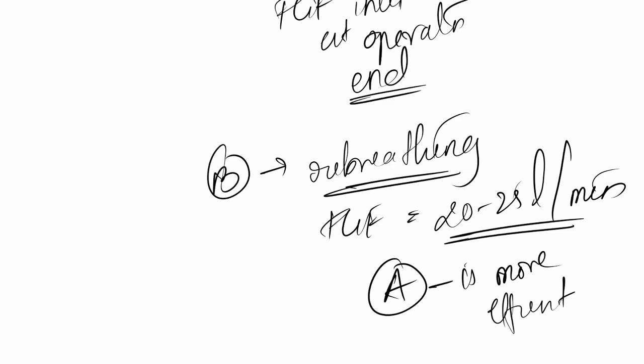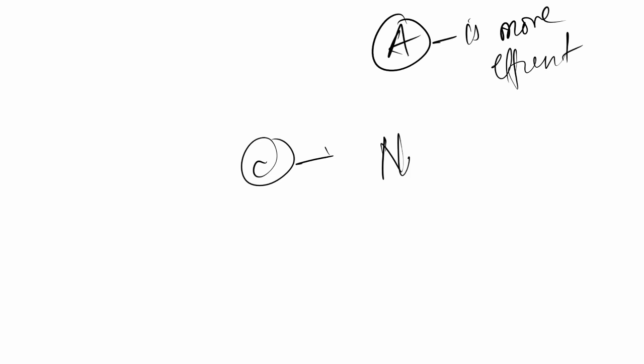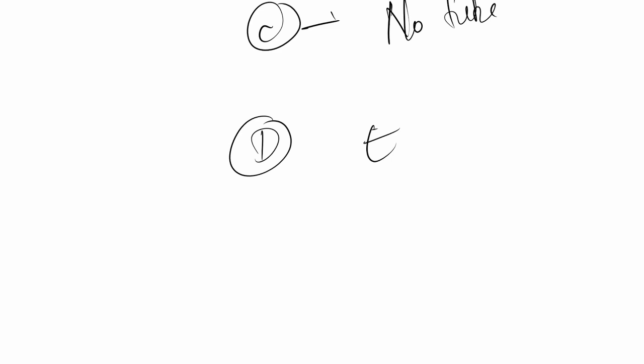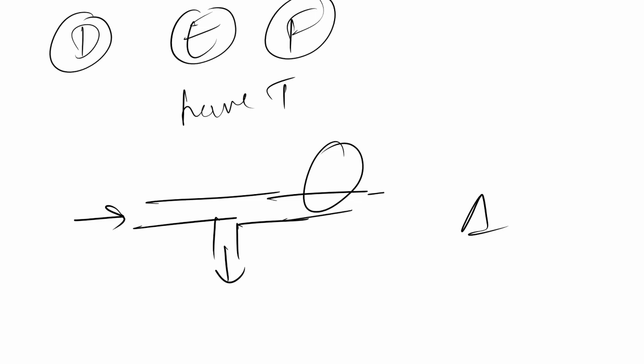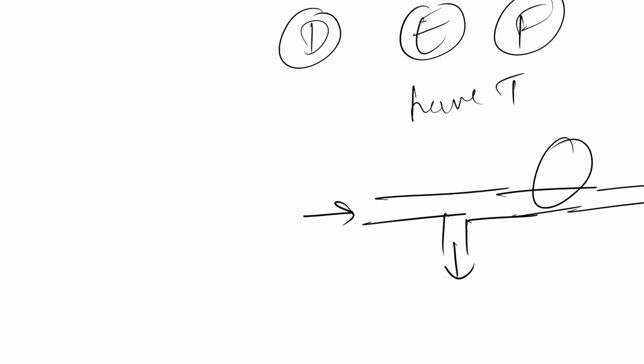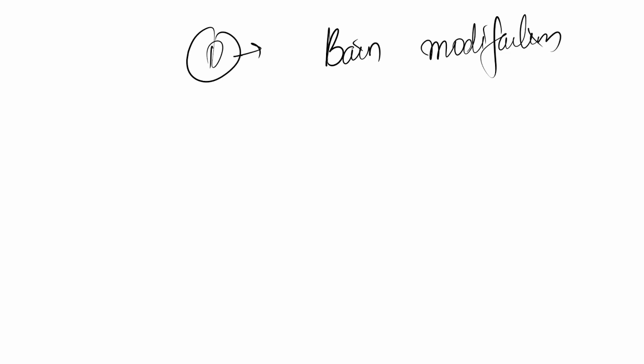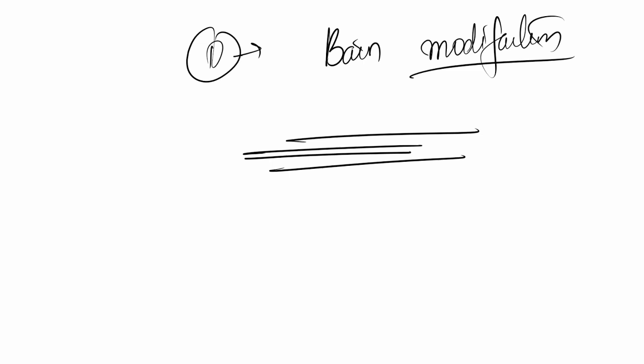Circuit C is a modification of B but without the corrugated tube. Circuits D, E, and F have T-piece modifications. A T-modification refers to a T-shaped junction where one arm is the inlet, one is the outlet, and one connects the reservoir to the mask. Circuit D has a modification called the Bain modification, in which the corrugated tube is replaced by a coaxial design: an outer tube and an inner tube, where the inner tube is the fresh gas flow input and the outer tube is the output.